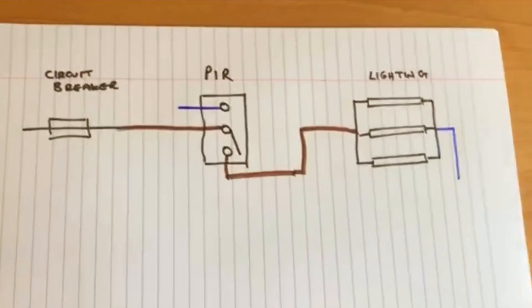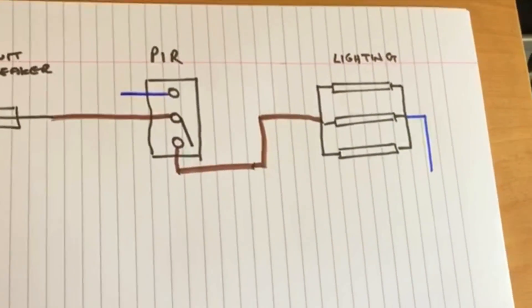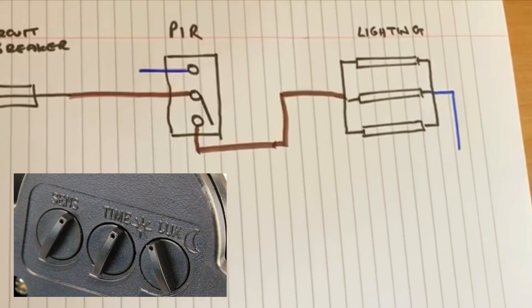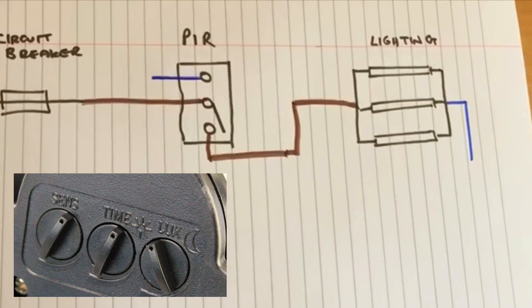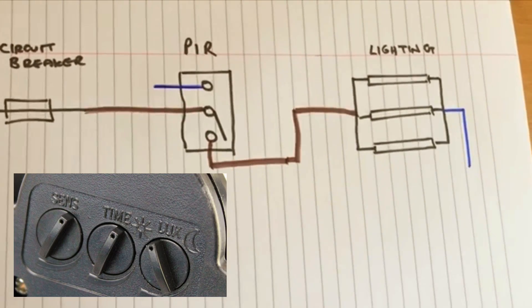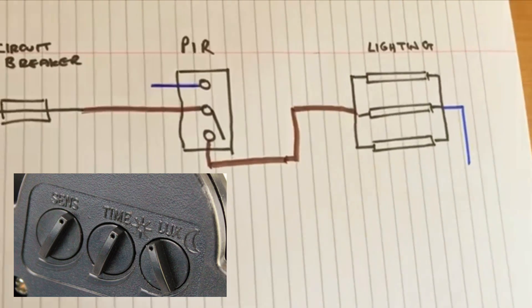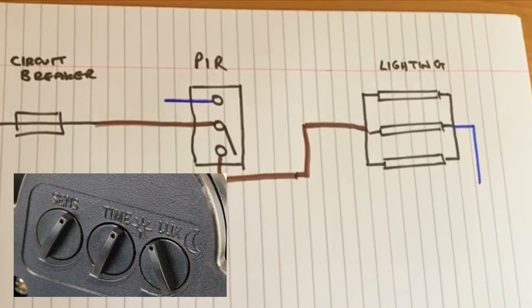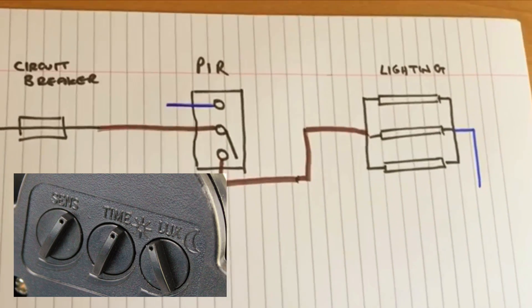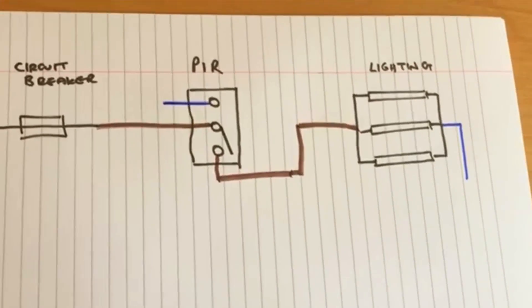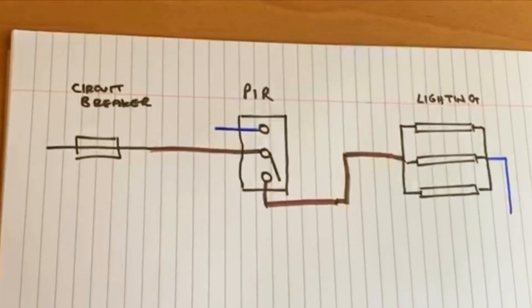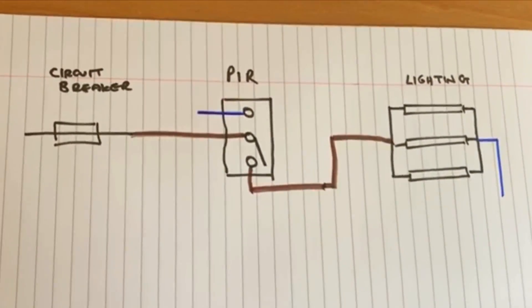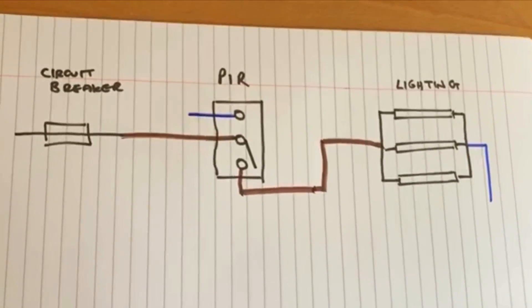PIRs also have a couple of controls on them. They have a time setting for how long they're going to stay on for, usually a minimum of maybe five seconds up to about a couple of minutes. They also have daylight and nighttime settings, but that's all relatively straightforward. The main thing for this video is just to understand the basic wiring for it, and as you can see, you don't get too much more basic than what this is.